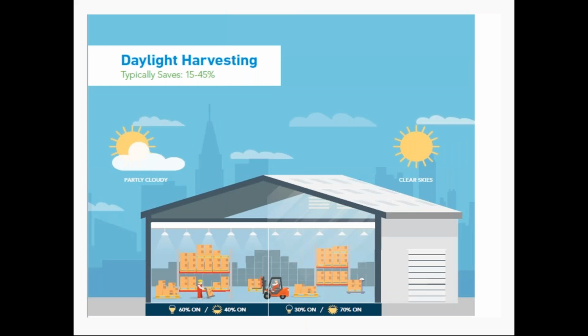Number two, daylight harvesting. If daylight is available, why use artificial light? That's an important question for this strategy. Daylight harvesting automatically regulates the use of electric lighting in a building in response to the amount of daylight available. Say you want to keep 30-foot candles in your area at all times - the sensor reads the amount of natural light coming into the space and adjusts the electric lighting to maintain those 30-foot candles at all times.